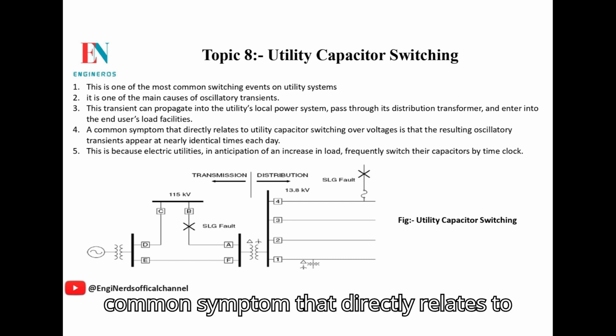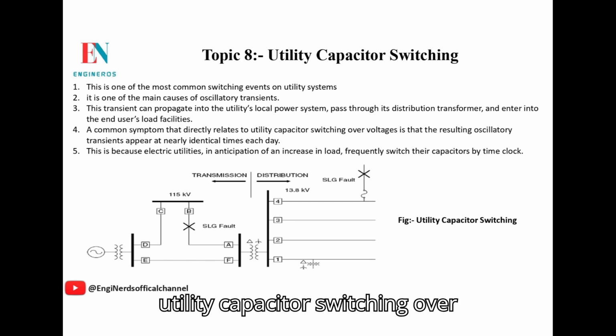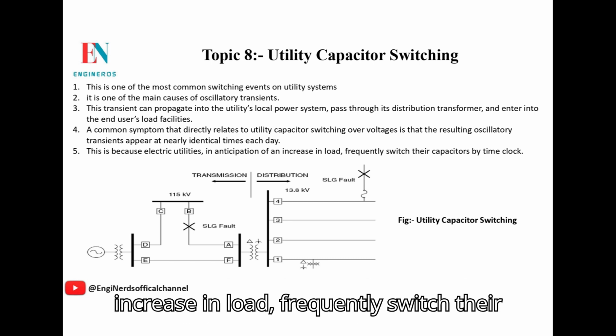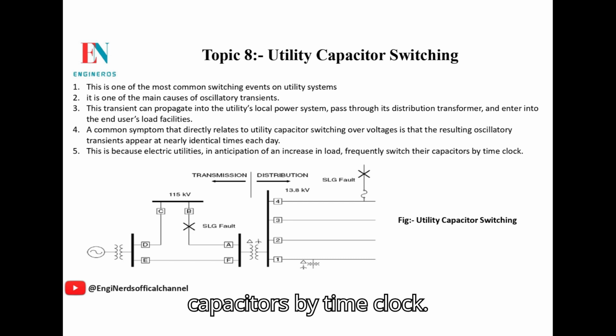4. A common symptom that directly relates to utility capacitor switching overvoltages is that the resulting oscillatory transients appear at nearly identical times each day. 5. This is because electric utilities, in anticipation of an increase in load, frequently switch their capacitors by time clock.